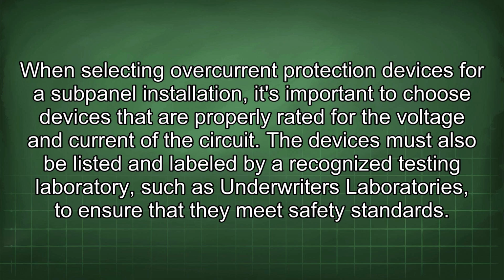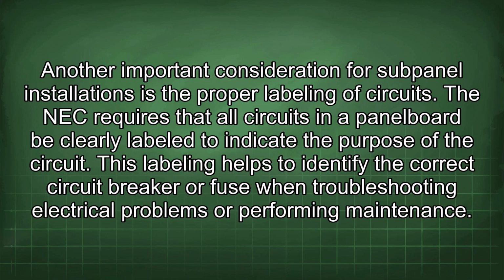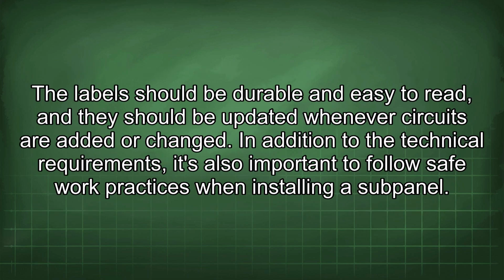they meet safety standards. Another important consideration for subpanel installations is the proper labeling of circuits. The NEC requires that all circuits in a panel board be clearly labeled to indicate the purpose of the circuit. This labeling helps to identify the correct circuit breaker or fuse when troubleshooting electrical problems or performing maintenance. The labels should be durable and easy to read, and they should be updated whenever circuits are added or changed.